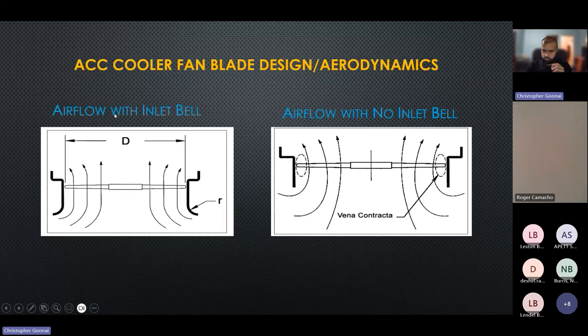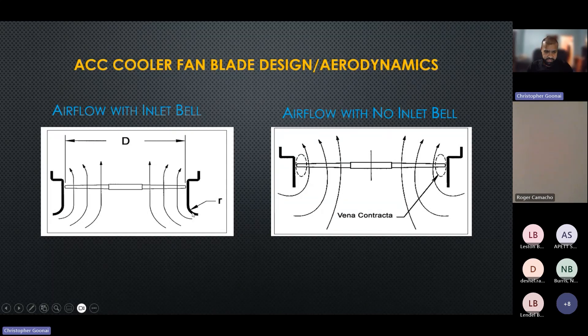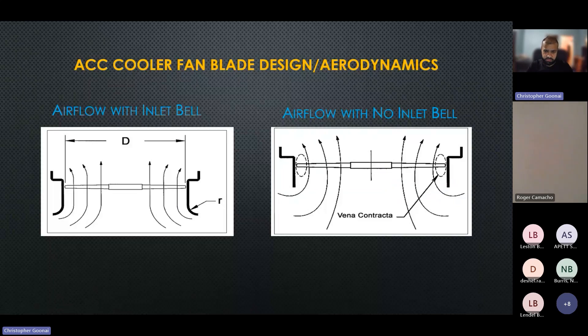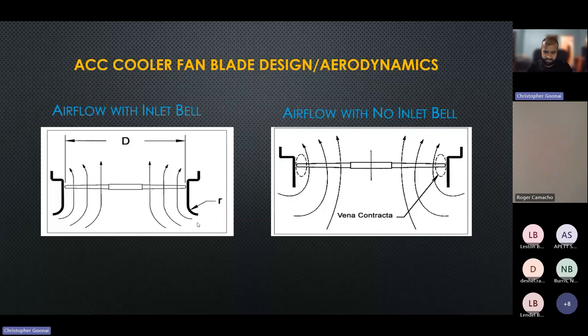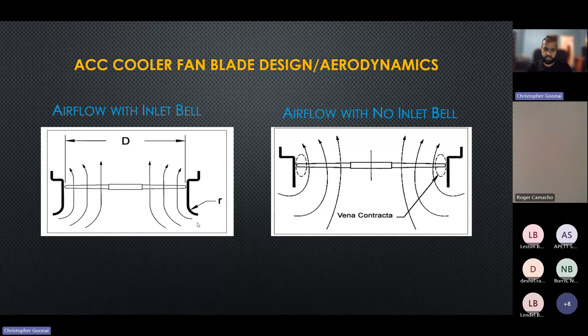These two design constructions illustrate the importance of the inlet bell. The inlet bell has a curvature for a distinct reason — it gives greater flow efficiency coming into the fan and expelling out. Without that curvature and flow efficiency, you tend to have vortexing at the tips, which is a region of high velocity and low pressure. Without the proper curvature on the inlet bell, you would have air loss and leakage at the tips.